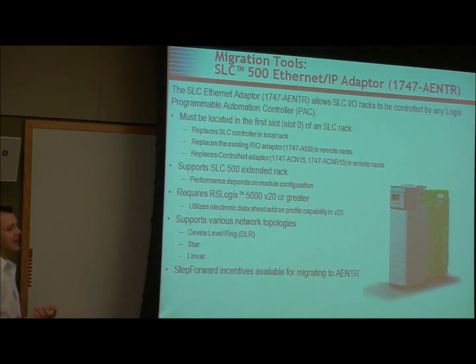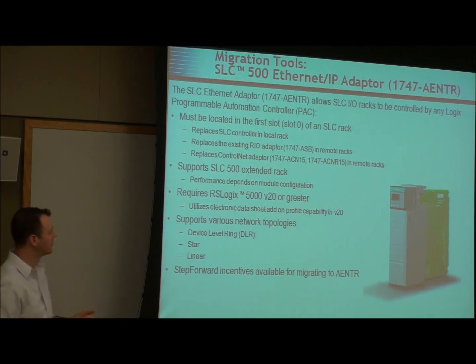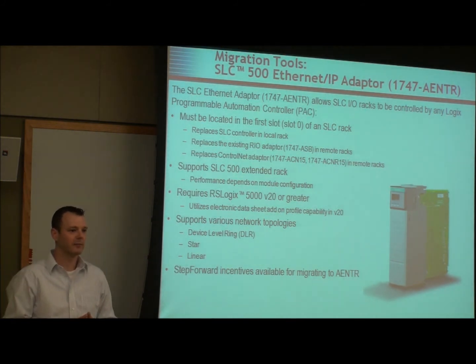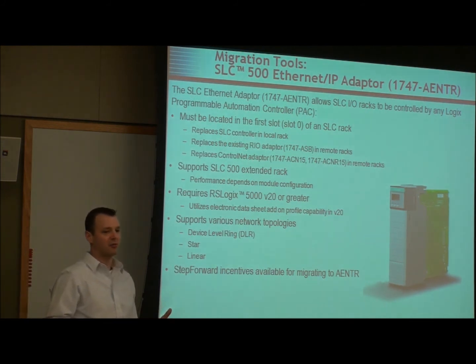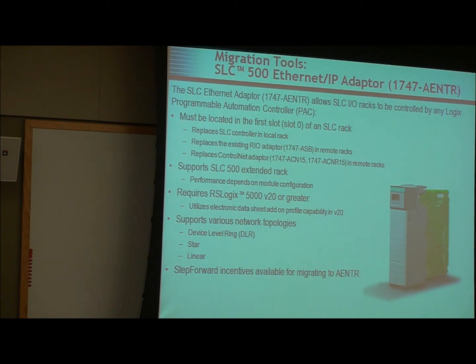This is the 1747 AEN-TR adapter. What it does is you literally pull out your SLC processor and put this in the same slot — or pull out your ASB adapter or control net adapter and put this in slot zero. Now your SLC I/O rack becomes distributed I/O for an integrated architecture system, which can be CompactLogix or ControlLogix. You don't have to replace all the I/O immediately. At some point it will become discontinued, but you can mitigate risk by doing a phased approach.